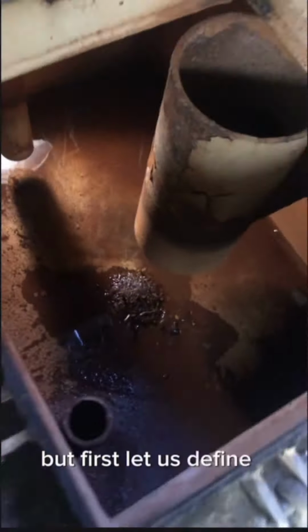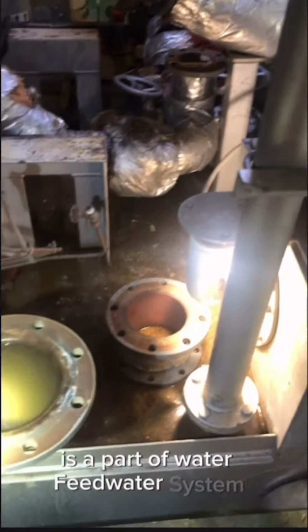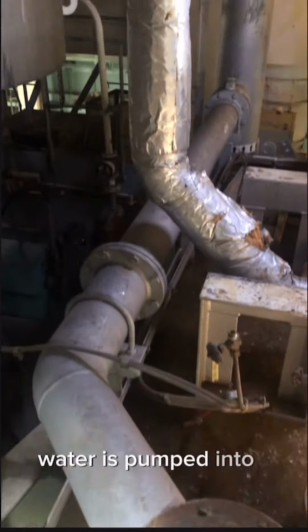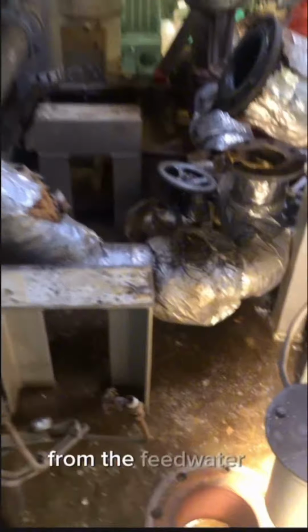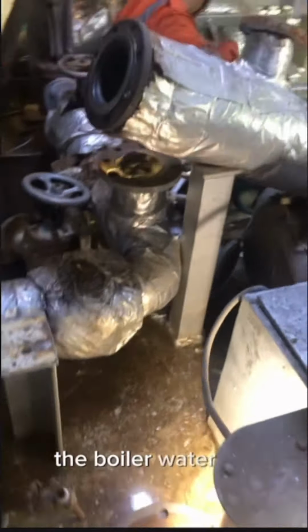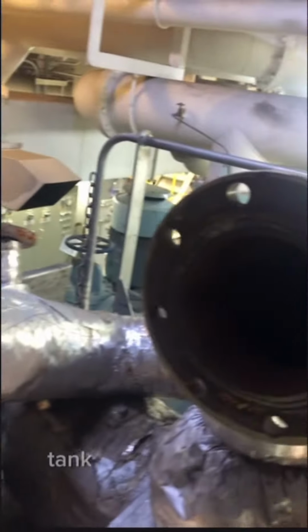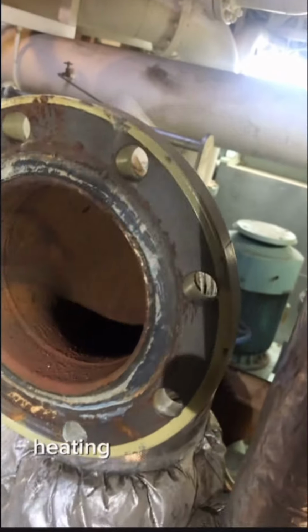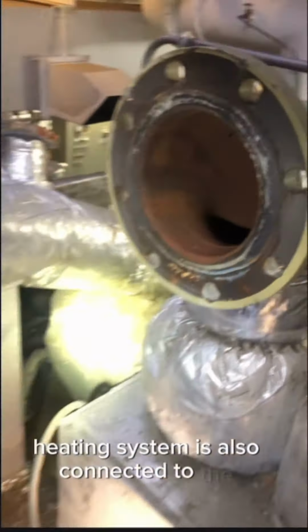Cascade tank, also known as Hotwell, is a part of boiler feedwater system. Water is pumped into the Cascade tank from the feedwater tank. The boiler water is treated in the Cascade tank, and the return from the steam heating system is also connected to the hot well.